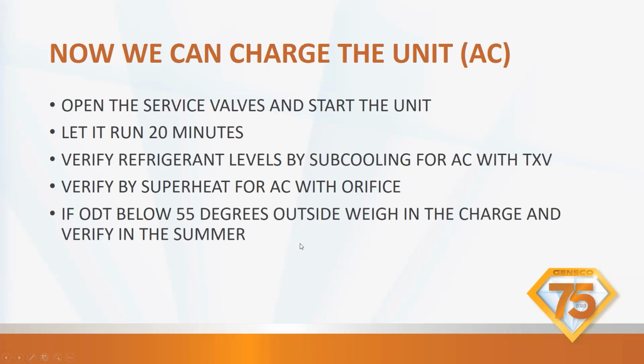So now that we've gone through, we've pressure tested our unit, we've evacuated our system down to 300 microns and it has not raised above 500. We know that the unit is ready to go. We're going to open up the service valves and we're going to start the unit. Okay. So we're going to open up the valves. We're not going to add any refrigerant. We're going to open the valves first.